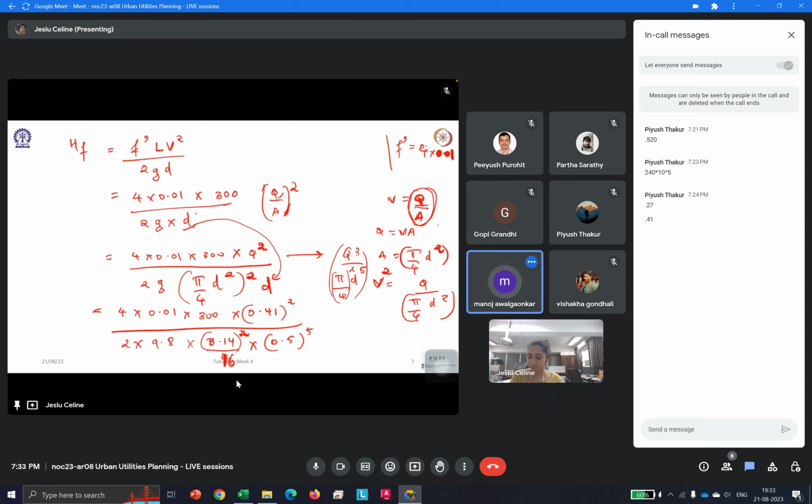Are you getting 5.35, ma'am? Yes, ma'am. So 5.35, approximately 5.4, is what we are getting over there. So our previous head was 40, which is due to the pump. Our total head would now be 40 plus 5.4, which is 45.4. So we have all the values that we need.